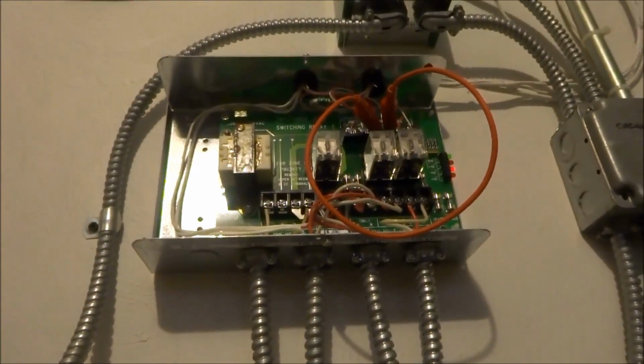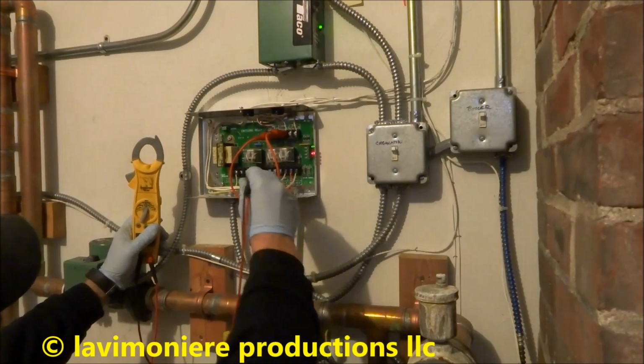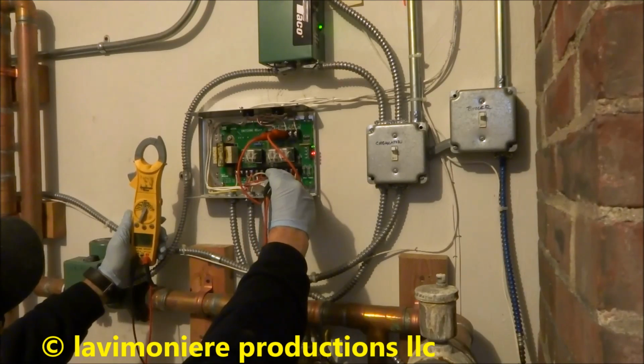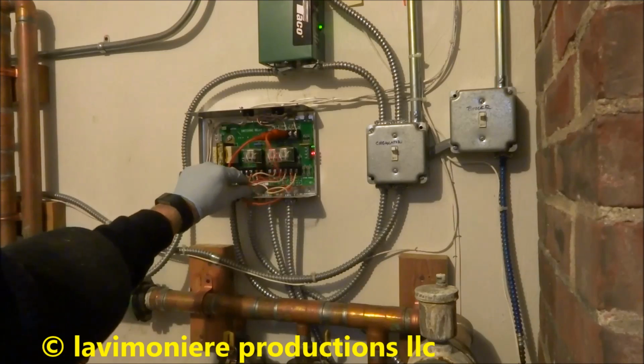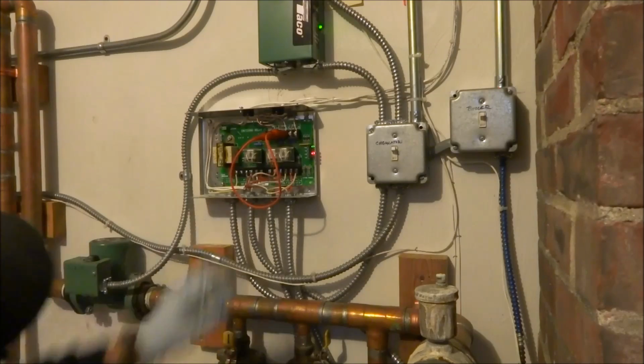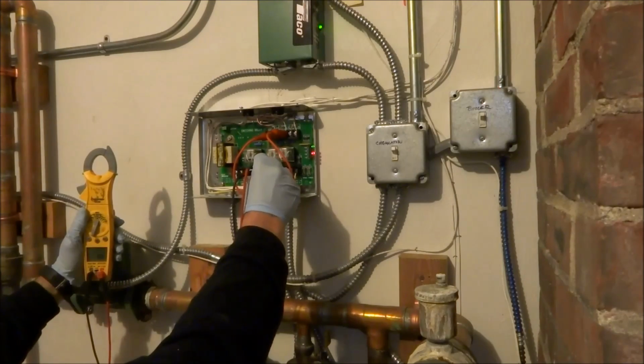I want to make sure I got power going down there. This circulator's bad. I'll have to check it. We'll check power. It's a 0015. I should have that in the truck. Yeah, look at, we got no power. It's a bad cube. That's why you check. Guys telling me, oh, it's a bad circulator. It's a bad circulator. I'm an engineer, I know it's a bad circulator. I'm an engineer, I know. Yeah, you know, alright.